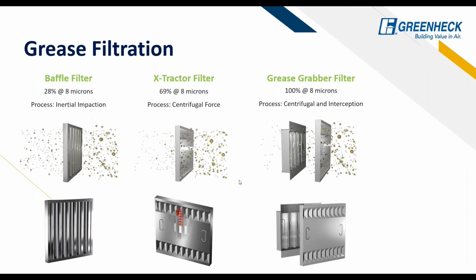Okay, so now grease filtration. So type 1 hoods require grease filtration. We have 3 different options, starting with the baffle filters. Going from left to right, we're looking at cheapest, least effective to most expensive and most effective, as well as pressure drop too. As you get to the grease grabber filters on that right, it's going to have a lot more of a pressure impact on your system there. And then you can see the process there.